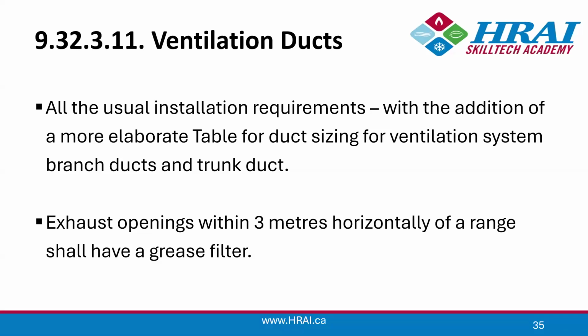And the only other note, I'm going to take you to that table in a second. The only other note in this section is that exhaust openings within 3 meters horizontally of a range shall have a grease filter. So of course your range hood has a grease filter. If you have an HRV intake within 3 meters, 3 meters is 10 feet, of a range, then it shall too have a grease filter. And that's commonly what we use in kitchens anyway. And probably best practice is just keep doing that, always require it.